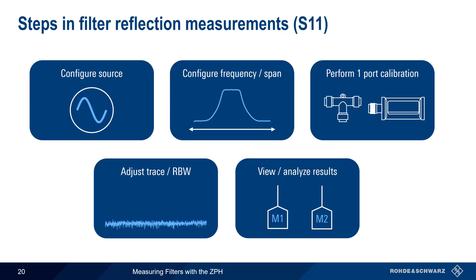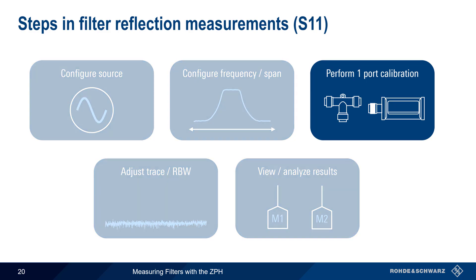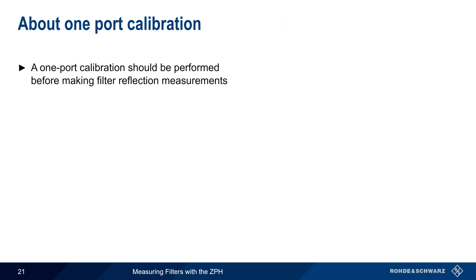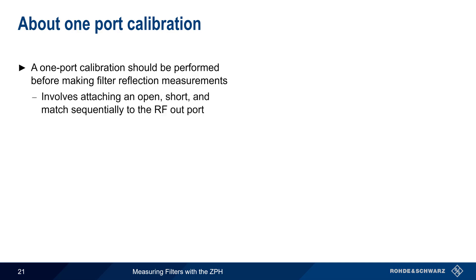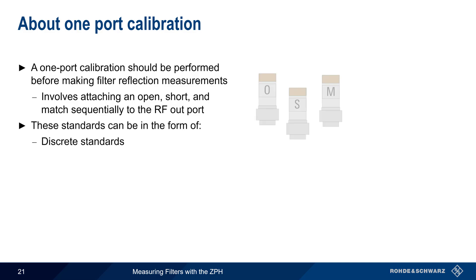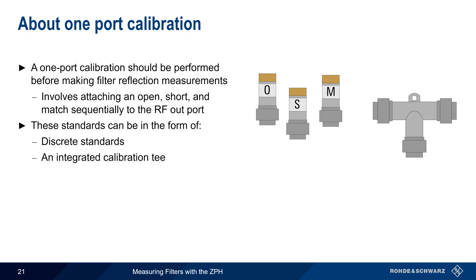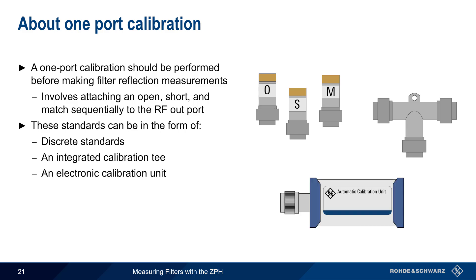The steps in making a reflection measurement are essentially the same as for transmission measurements with one exception. Instead of performing a normalization using a through, in reflection measurements we need to perform a one-port calibration using a set of calibration standards. A one-port calibration should be performed before any reflection measurement, and this process involves sequentially attaching an open, a short, and a match to the tracking generator, or RF output port. These standards can be in the form of discrete standards, or may be combined into a calibration T. In addition to these manually attached standards, electronic calibration units can also be used — these switch the standards in and out automatically and are controlled by the ZPH.